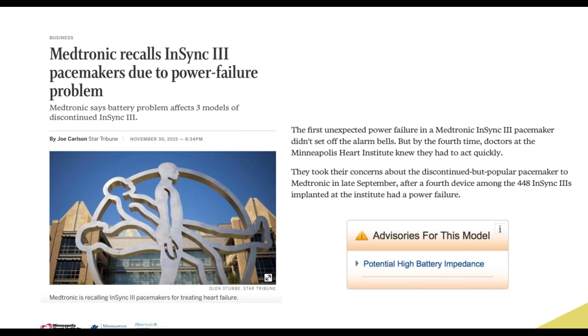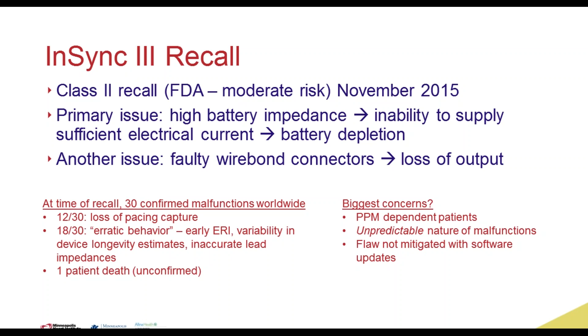The primary issue was found to be high battery impedance, which led to an inability of the device to supply sufficient electrical current, and that led to rapid battery depletion. There was also another issue, which was found to be faulty wire bond connectors, which were of inferior quality and led to loss of output on the affected channels and the leads. The biggest concern for pacemaker failure and unexpected battery failure would be in the pacemaker-dependent population. So they would potentially have a loss of therapy that sustains their life at any given time. And also this flaw could not be fixed with any software or programming updates. That's an important part here.